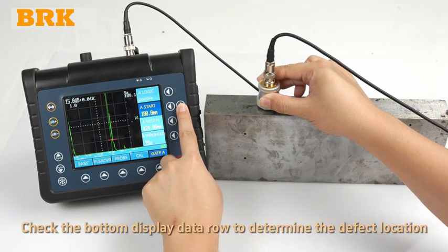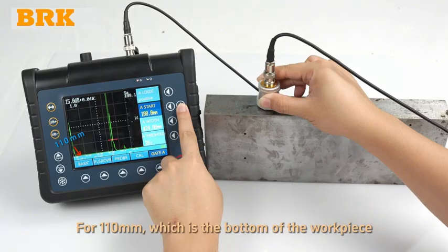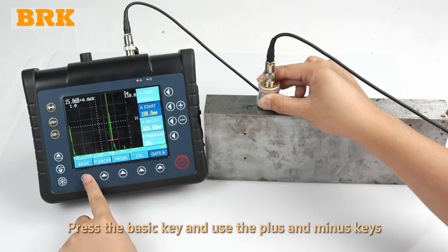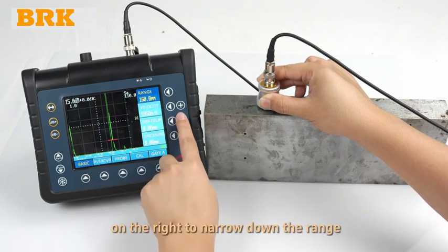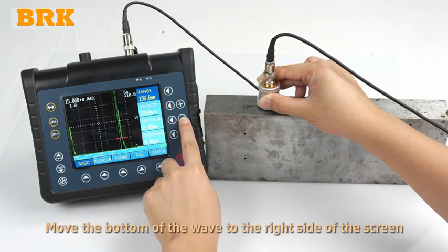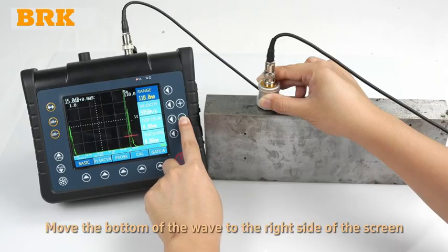Check the bottom display data row to determine the defect location. 110 millimeters, which is the bottom of the workpiece. Press the basic key and use the plus and minus keys on the right to narrow down the range. Move the bottom of the wave to the right side of the screen.